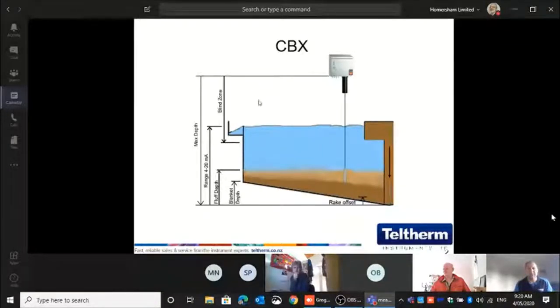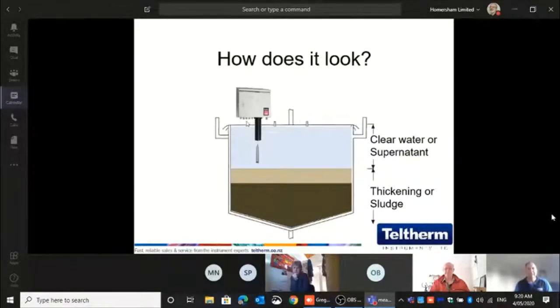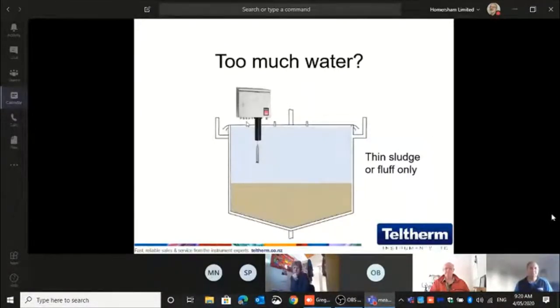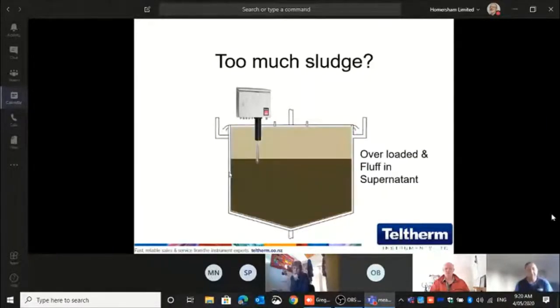So the sludge blanket system basically is what we call a yo-yo sensor. The sensor sits in here, goes down, measures whatever you need to measure, sludge, fluff, and goes back up. While it does that, it sprays water onto the sensor when it goes down, basically to wet the sensor. And when it goes up, it sprays the cable and the sensor clean as soon as it's in there. This is basically what you want to see. This is what you basically, yeah, that's not very good. And that is very bad.